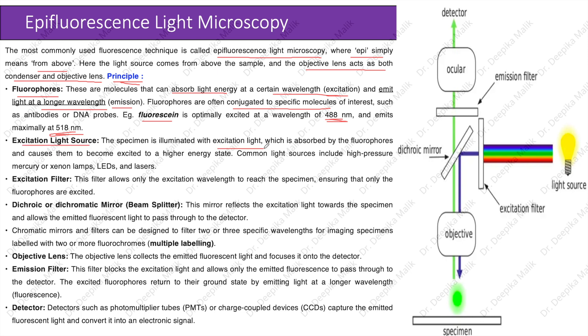The excitation light source: the specimen is illuminated with excitation light, which is absorbed by the fluorophores and causes them to become excited to a high energy state. Common light sources include high-pressure mercury or xenon lamps, LEDs, and lasers. The excitation filter allows only the excitation wavelength to reach the specimen, ensuring that only the fluorophores are excited.